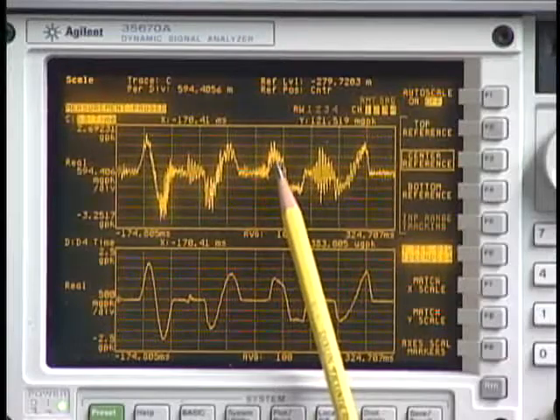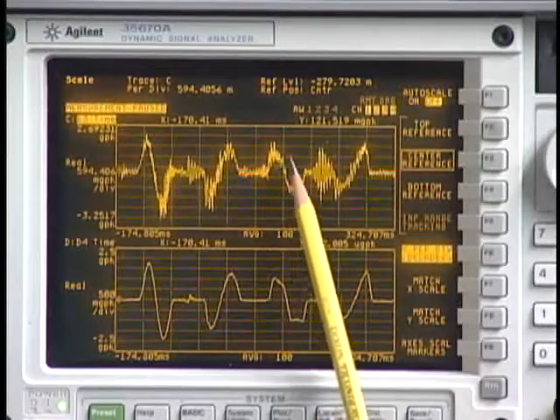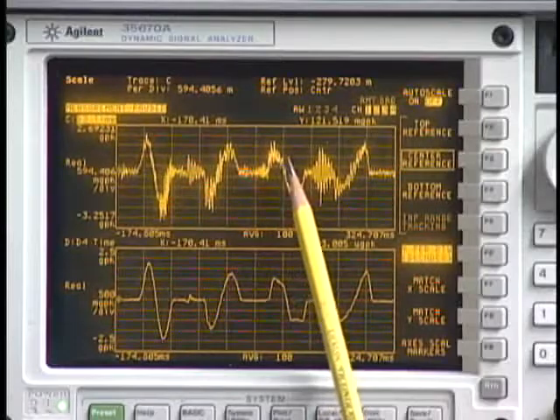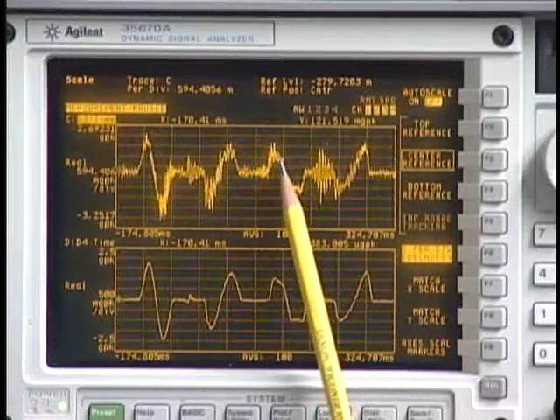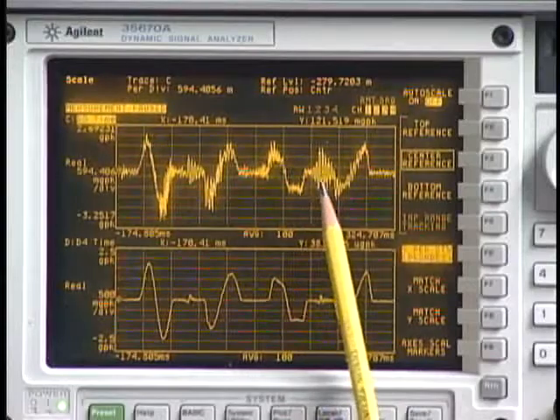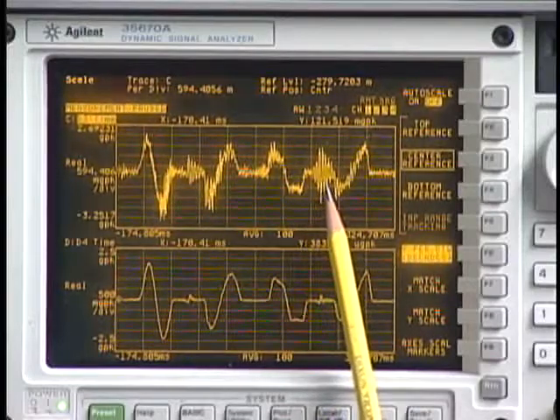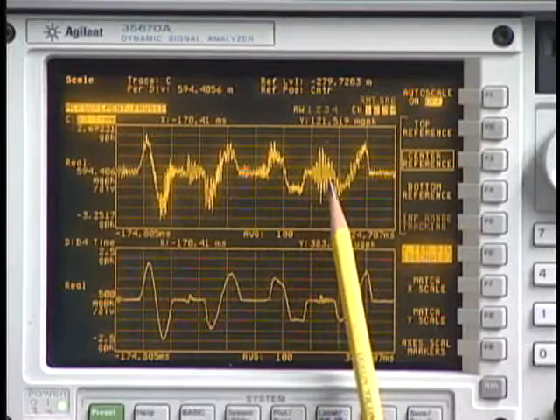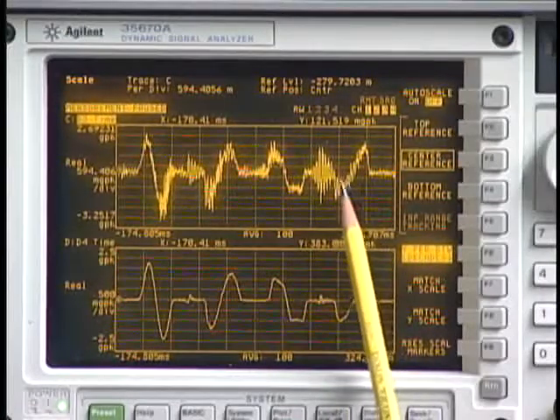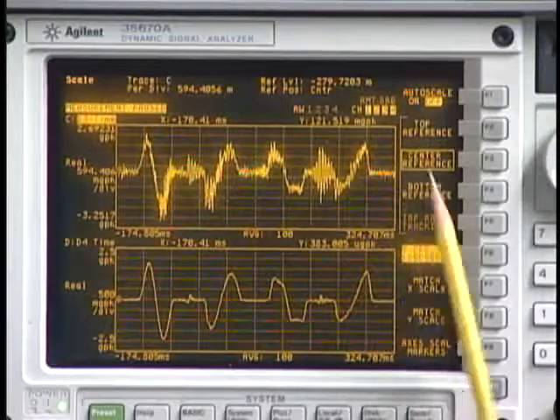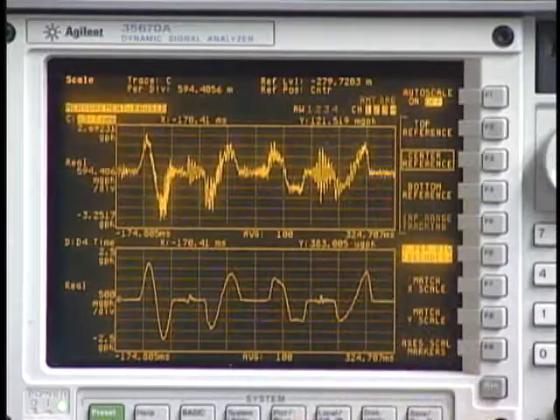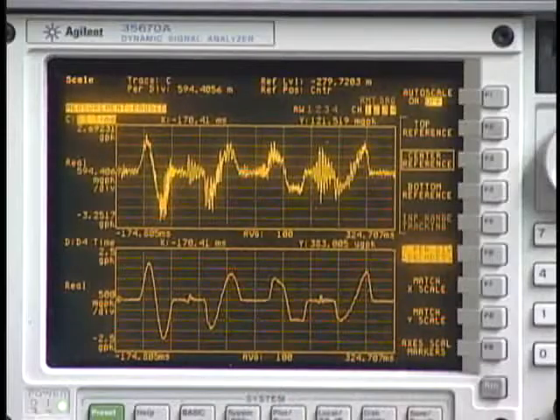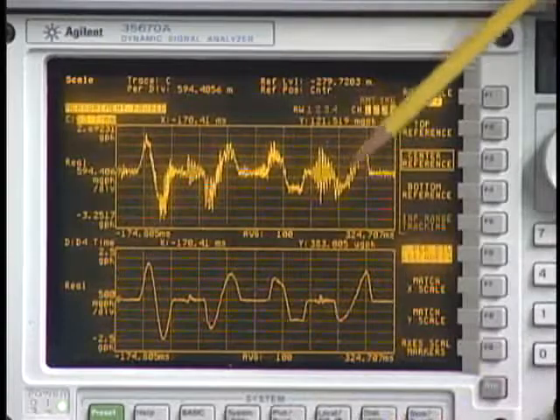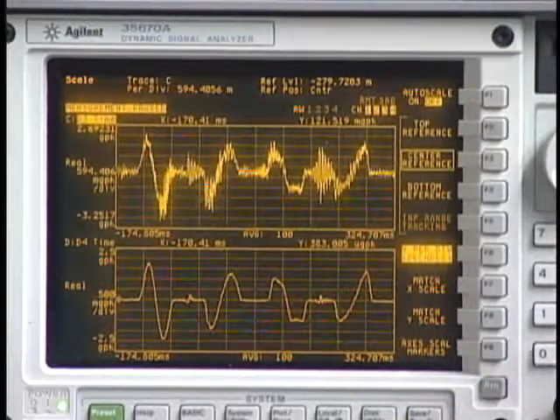Then we come to the modified trapezoid rise, which also has a lot of ringing on it. That's in part because of the roughness of the jerk in the modified trap function. And here we are at the second crack on the other side, 180 degrees away, and that again rings the system quite drastically. And finally, we have a modified sine fall. Now, this is typical of the kinds of traces you get from accelerometers in real machines. In fact, this is relatively quiet, that is less noisy in terms of these oscillations than you would see in a real machine, because we have here a laboratory instrument running in a quiet environment.